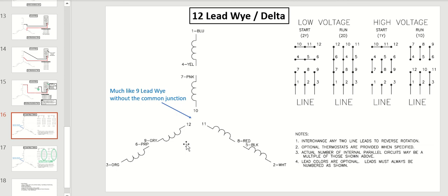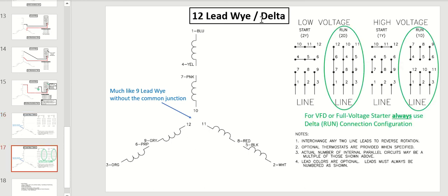The last motor is the 12-lead Y delta motor, and this is much like the 9-lead motor in the Y configuration, except this common junction here is split out where we have wires 10, 11, and 12. So the 12-lead Y delta motor can be used as a 2Y or a 2D, a 1Y or 1D, just like you saw with the 9-lead Y motor and the 9-lead delta motor. But it's very important with the 12-lead Y delta motor, and I would like to do another video in the future that explains the Y delta starting configuration.